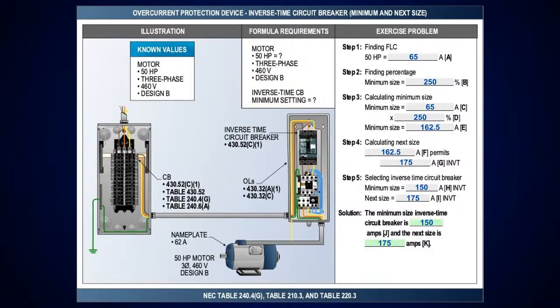So when I look at this next, it's an inverse time circuit breaker, and if I look at the table for my 50 horsepower, 460 volt three-phase design B, it's going to tell you take it at 250%. So if you notice, based on the table, for non-time delay, we took it at 300%, time delay 175. Then when I got up to my instantaneous, I took it at 1100%. Then I had to look at C3, which allowed me to go to 1700%.